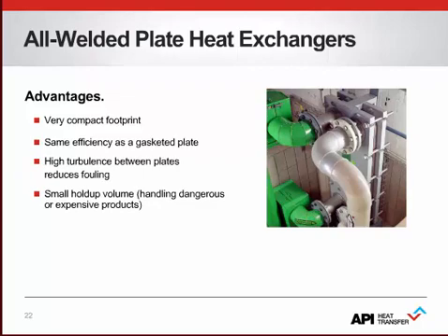The advantages of the Sigma WIG type all-welded plate heat exchanger show the similarity to the gasketed plate heat exchangers: the small footprint, the high efficiency, as well as the hold-up volume. As the all-welded plate heat exchanger cannot be opened like a gasketed plate heat exchanger, it is a big advantage that the high turbulences in the channels make sure that there is a good self-cleaning effect.